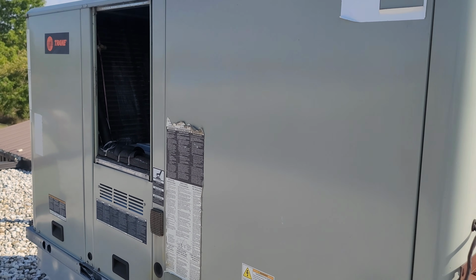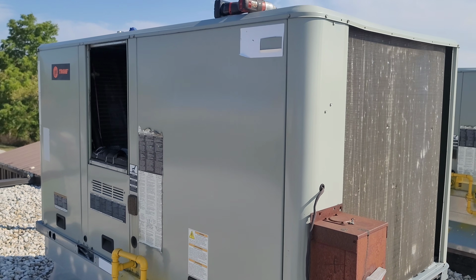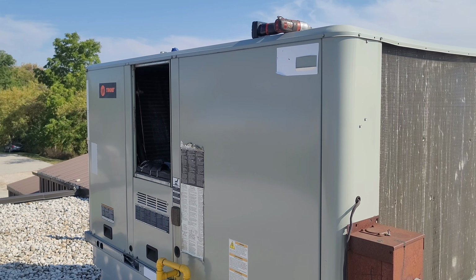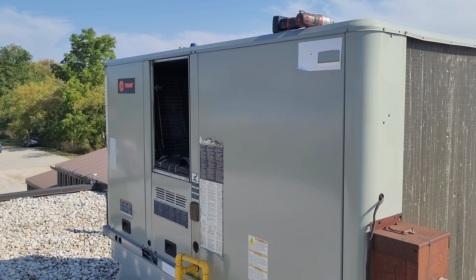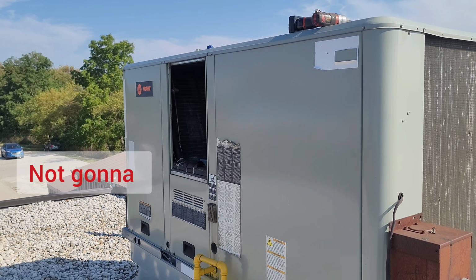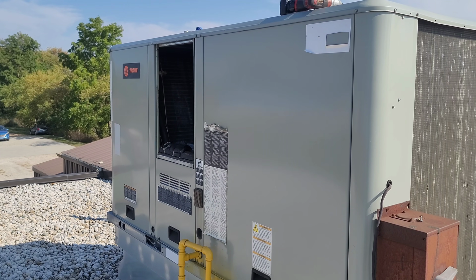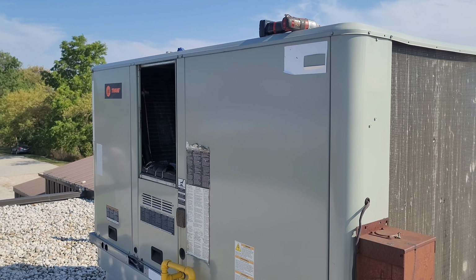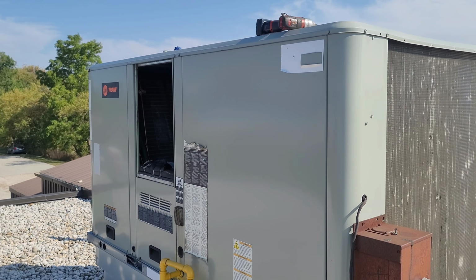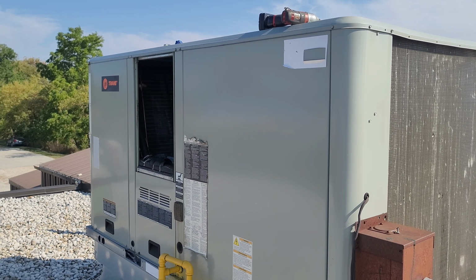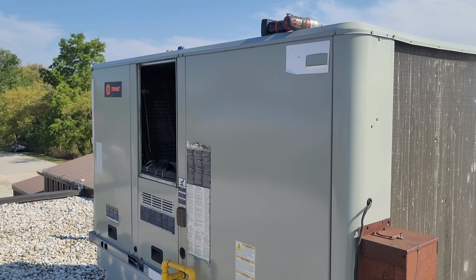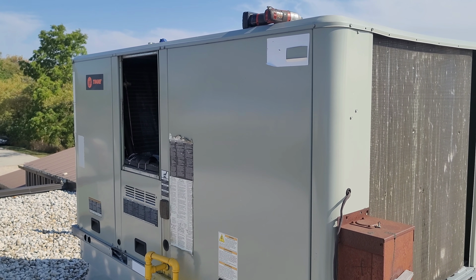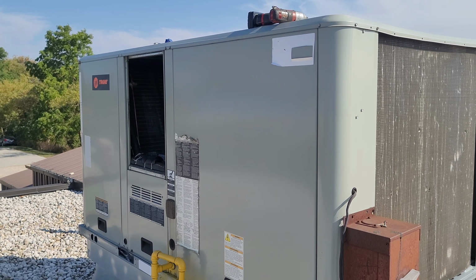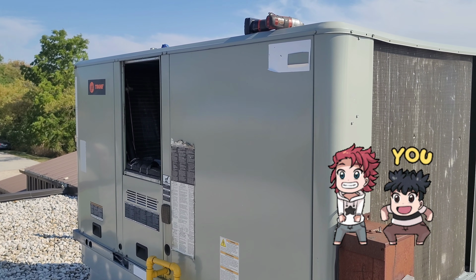Okay, our unit is working, both stage compressors are working, so we're gonna recommend the economizer control board to the customer. But with my experience, they're not really gonna approve it, because most of the customers, when we explain the function of the economizer and let them know the cost and everything, they barely approve. So far right now I have bypassed the economizer completely, properly jumped it out, and now the unit is working. So we have tested everything, and the unit has proper refrigerant inside the circuit. So see you next time.